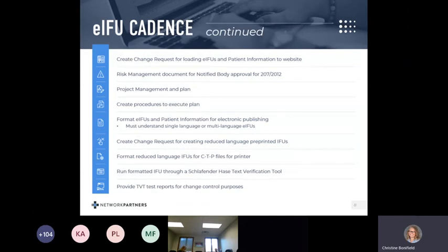If you're going all the way to 207-2012, you'll need to do your risk management exercise first. You'll have to document that you're not creating or increasing any potential risks. You should be able to show that e-labeling mitigates the risk of losing the paper IFU, but you'll have to address the issue of internet accessibility.